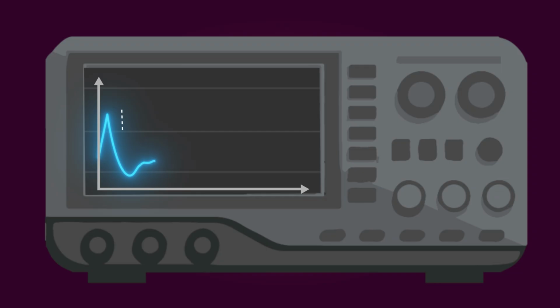Let's talk about waveforms. That's where we get into the juicy engineering part. When you look at the current versus time waveform during the power up of a device, you'll see something like this. Right at the beginning, when power is applied, current spikes sharply to a peak value. This peak might be 5 times or 20 times higher than the normal operating current. After a few milliseconds, it decays exponentially and stabilizes to the steady state current. For example, if your normal current is 1 ampere, then inrush can easily be up to 10 amperes or more for a very brief moment. Typically, this inrush current lasts from a few microseconds to a few hundred milliseconds.